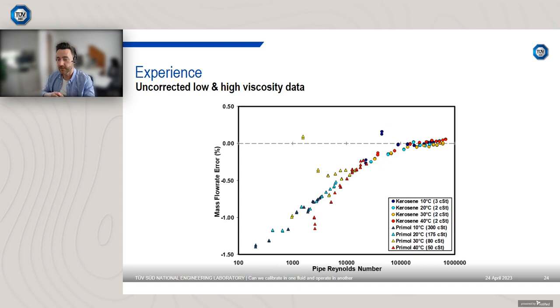I have a journal paper that discusses zero effects, and also a good practice guide that's freely available on our website. I'm not going to discuss it in too much detail today. But what you can see here is a clear Reynolds number effect. With decreasing Reynolds number there's an increasing underread, and all the way down to approximately 300 to 400 Reynolds number, we're underreading by approximately 1.5%. That's very significant when Coriolis meters are 0.1% devices. So for high viscosity fluids, it certainly looks as if there is a viscosity or Reynolds number effect.